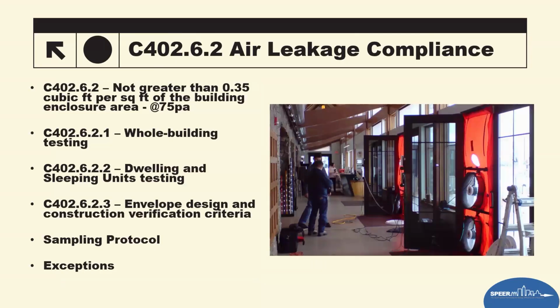So air leakage testing for commercial building was broken into sections allowing for options and must be tested by a third party, approved third party. I won't go through the whole detail of that. It is lengthy for that part of it, but it's also based on size of the building. We're looking at a different pressure reading, which is 75 pascals, not 50 pascals. It's 0.35 cubic feet per minute per square foot of the enclosure area, not an ACH.